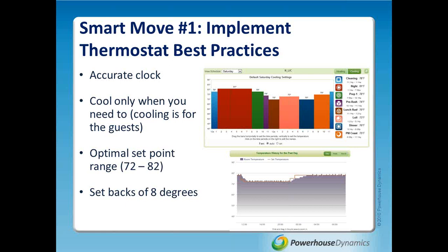Great, good points, guys. I would only add, to the question about set points, there are numerous studies, EPA and others, that have shown every degree that you move that set point is 2 to 3% of your cooling costs. So if you're thinking to yourself, I could never get away with 72, I actually have to be at 70, and even that's pushing it, that could be close to 5% of your cooling costs, and that could be somewhere in the $500 to $1,000 range just for the summer season, which is not insignificant if you put that in terms of the number of customers you need to get through the door to make up that lost cost. I might suggest it's somewhat of a risky bet to make that decision.